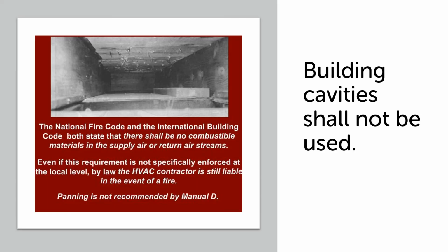Building cavities shall not be used. So the National Fire Code and the IBC both state that no combustible materials. And that includes building cavities, and that includes you can't run wires and pipes through your ducts. And even if this requirement isn't specifically enforced at the local level, by law, the HVAC contractor is still liable in the event of a fire. Panning is not recommended by Manual D. So please just stop doing this.